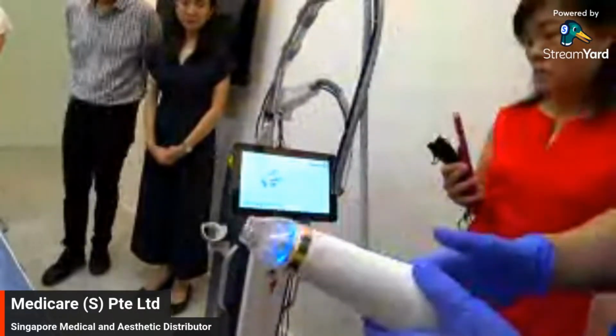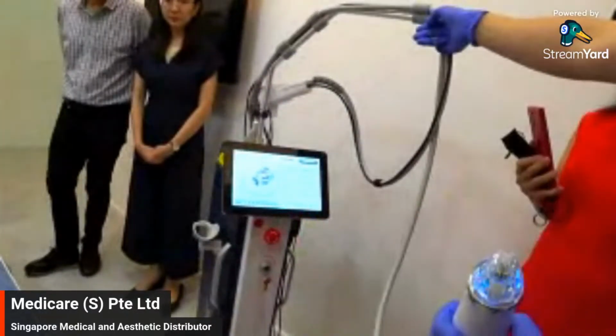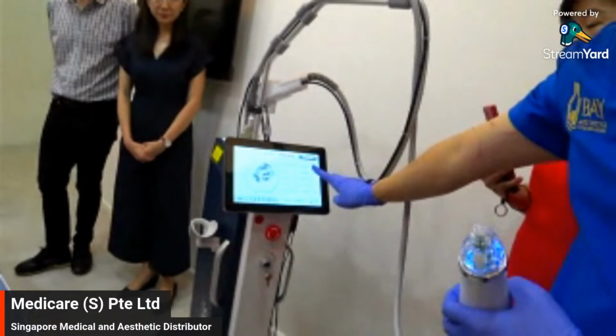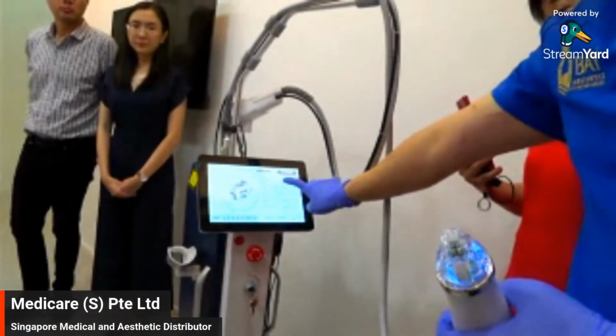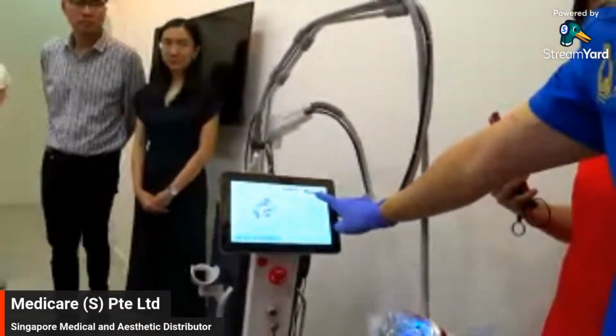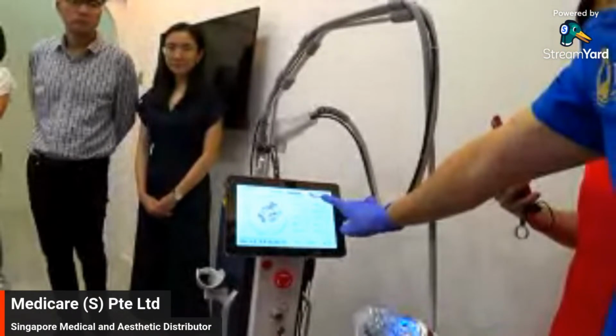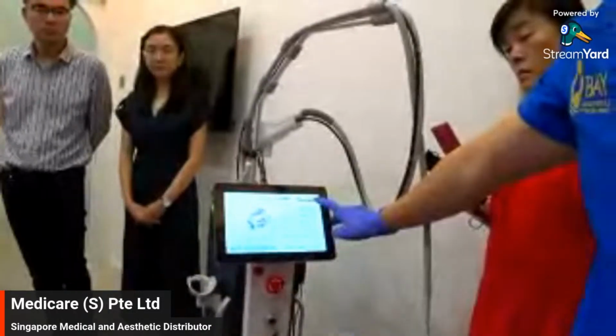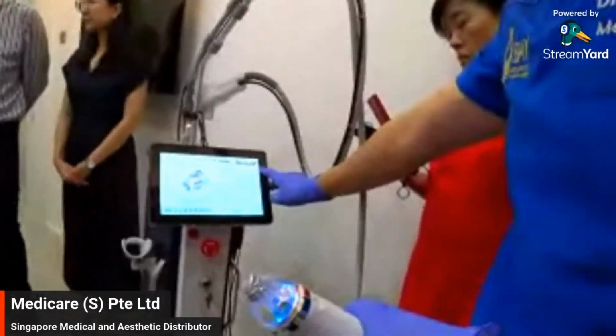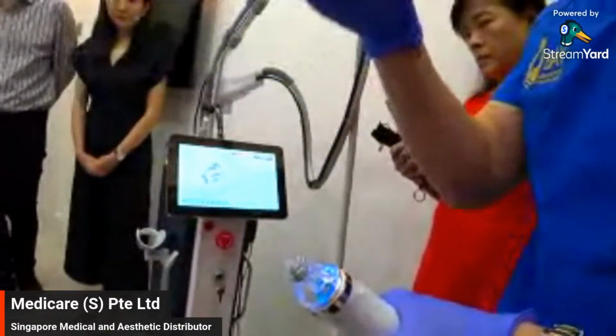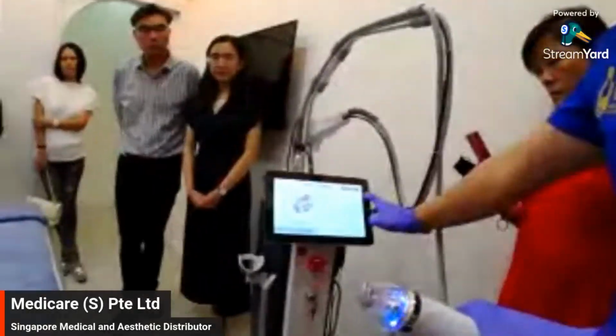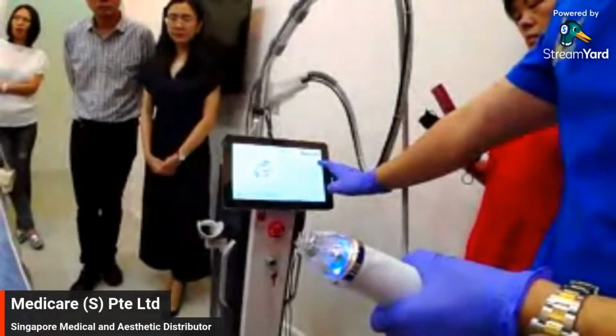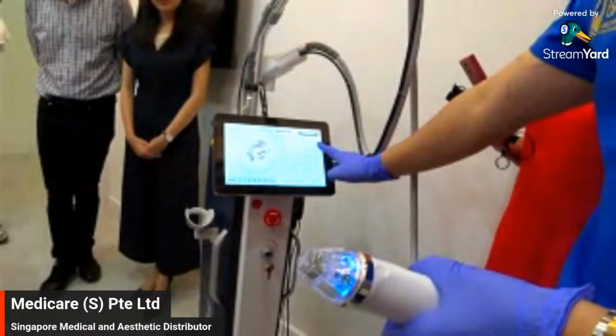Okay, so now that we are in, this is what the interface looks like. As I mentioned, for intensity you can go all the way up to 100, but most of the time we're working between 30 to 50% RF intensity. I've never exceeded 50%. The usual factory recommendation is between 40 to 50%. So I would say somewhere between 30 to 50, and you don't need to go above that.